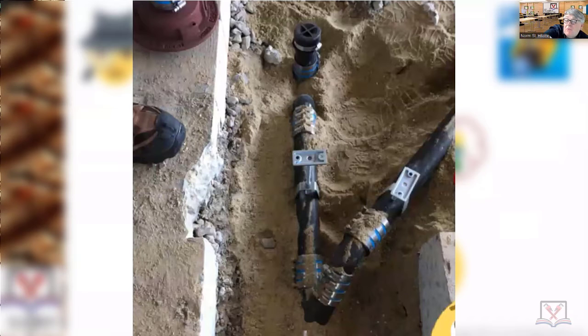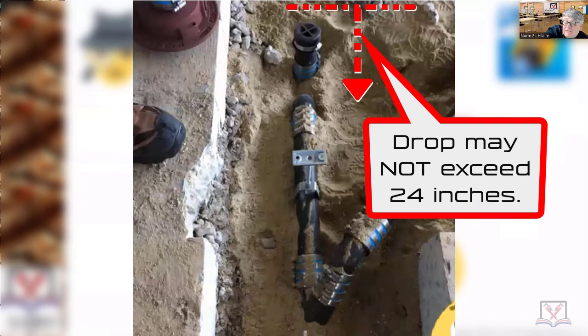The drop from wherever the fixture strainer is — whether it's a floor drain, floor sink, or you're installing a kitchen sink — you should never exceed a drop of 24 inches from the fixture outlet to the crown weir of a trap.